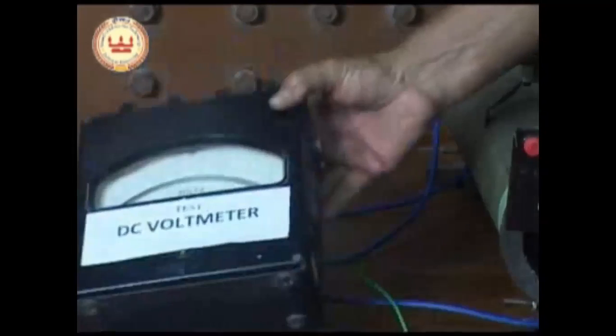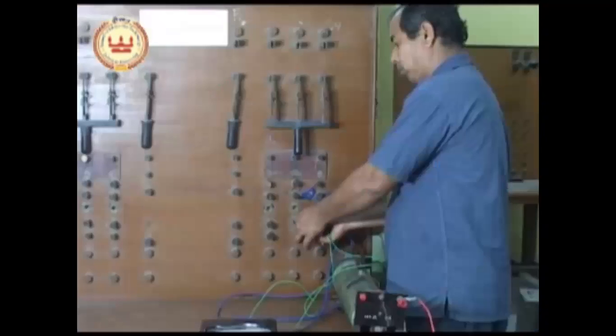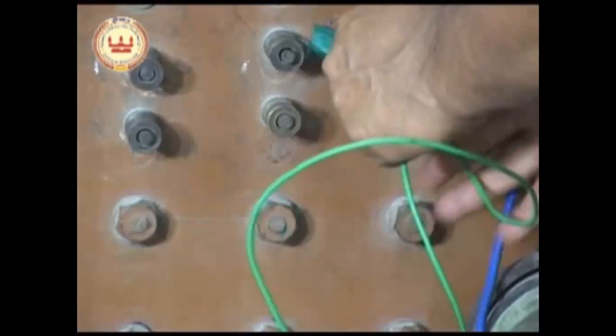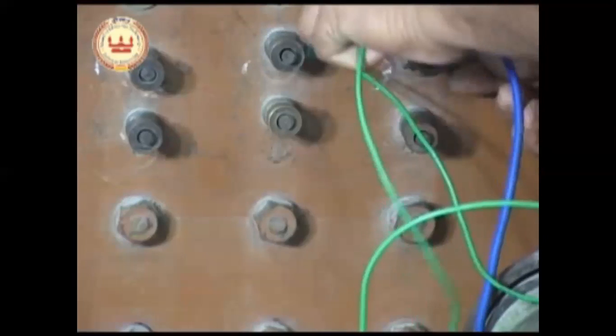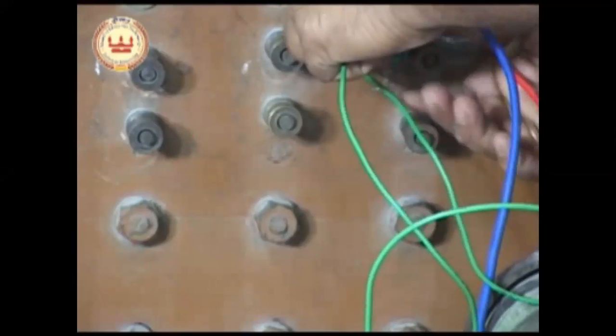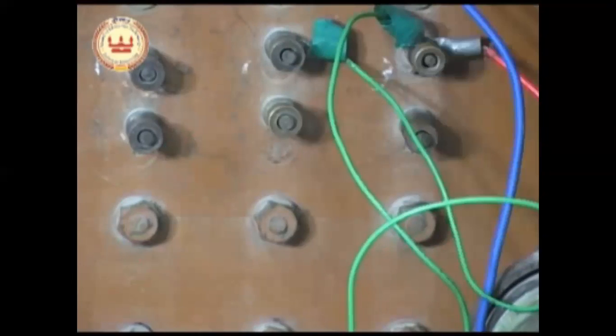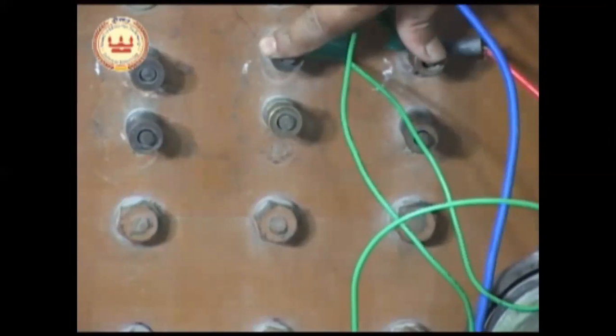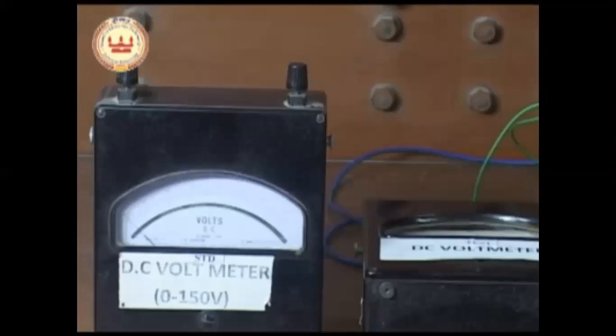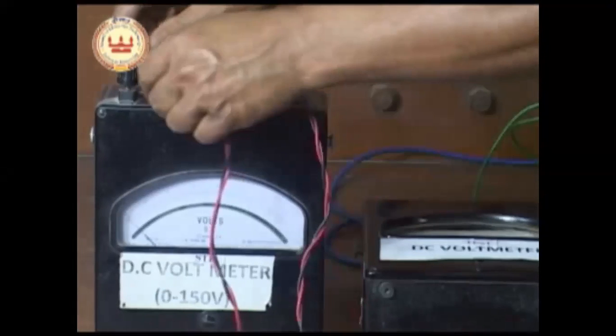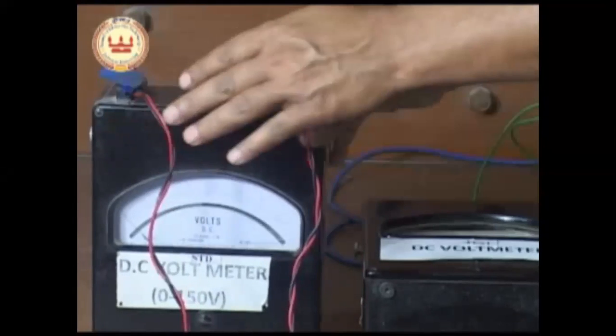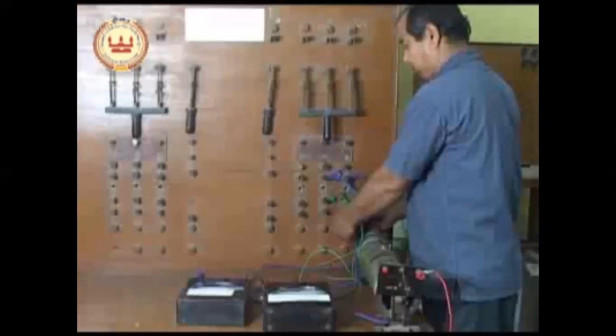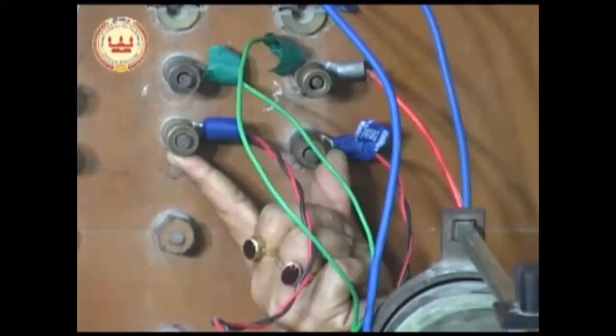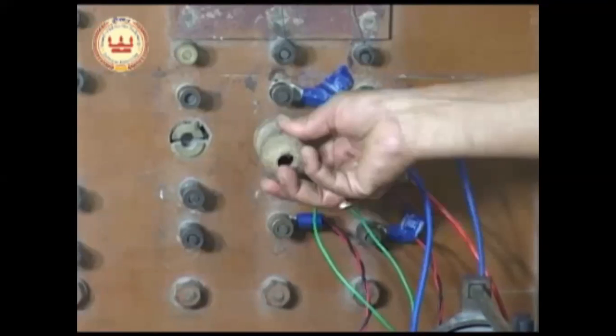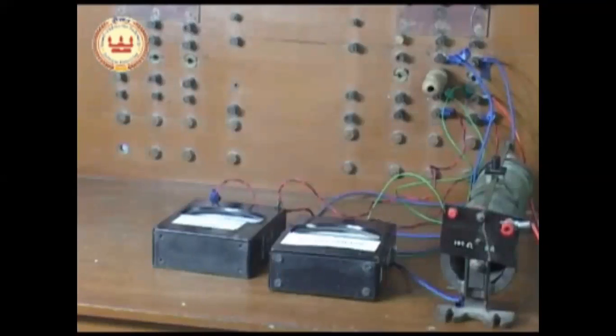This is the first voltmeter to be connected. Hence, this voltmeter is connected in the range of 0 to 75 volt DC across these two terminals, and this is the second one, and the second voltmeter is connected in the range of 0 to 150 volt DC across these two terminals. These two terminals should be shorted to complete the circuit. Thus, the circuit connection is completed for calibration of voltmeter.